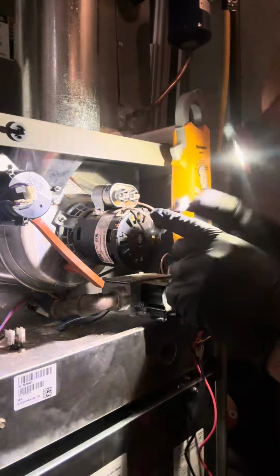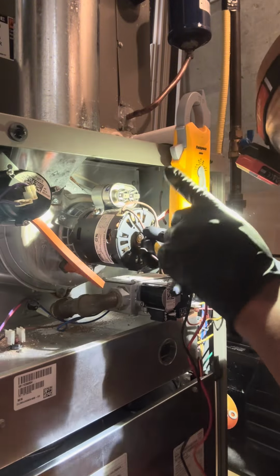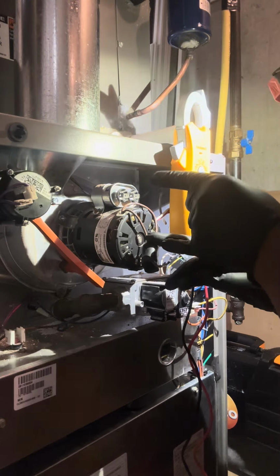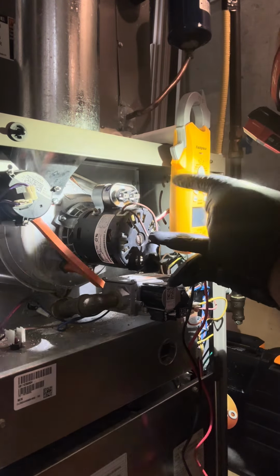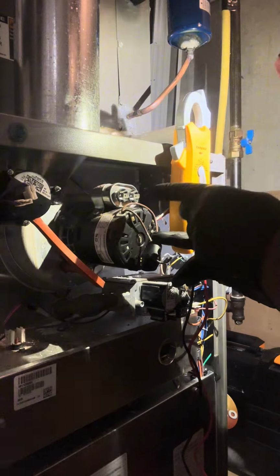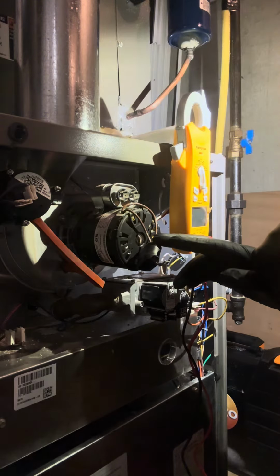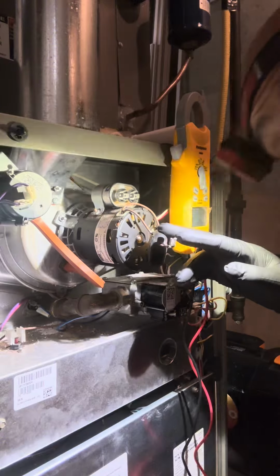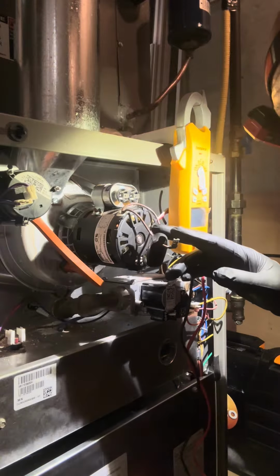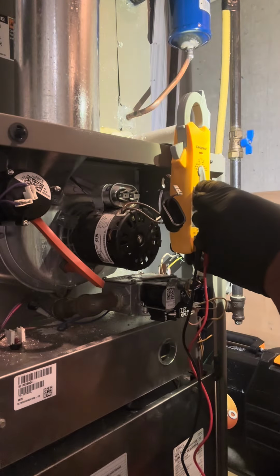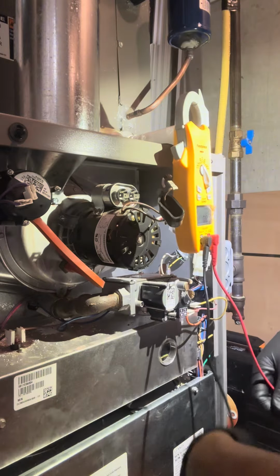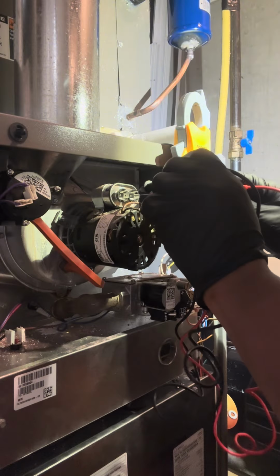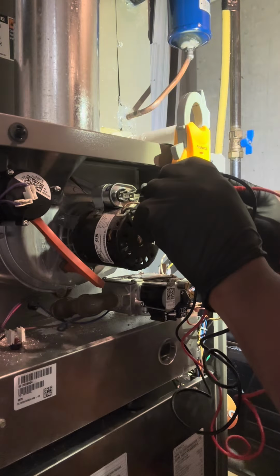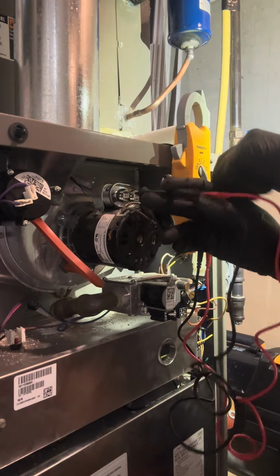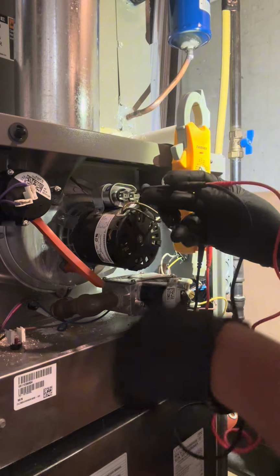You got to remember, these things are batteries. Like any battery, even when it's not running, it has potential energy stored inside of it, and it is a risk of shocking yourself. So the perfect way to do it, the old school way, was to just put a screwdriver across the tube. But you know, obviously we've evolved since those days. So I'm going to set my meter to ohms, and I'm going to go across the connections and just make sure it reaches 0. And then I can switch to microfarads and I can test this.